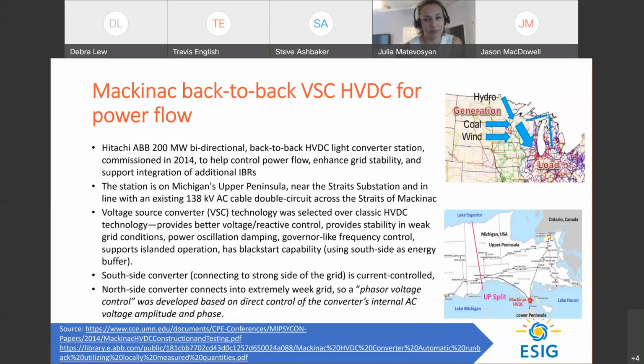Basically, at the Upper Peninsula, the grid is relatively weak, and they were seeing more inverter-based resources coming into the grid, and that forced the power flow along a long transmission path towards the south, the Lower Peninsula, where most of the load is connected. Also the connection of the Upper Peninsula is relatively weak to the rest of the grid, and there exists a possibility of disconnection on the Upper Peninsula side. Previously the grid was supplied through 138 kV lines from the Lower Peninsula. So what they did now is install that HVDC Light converter station.